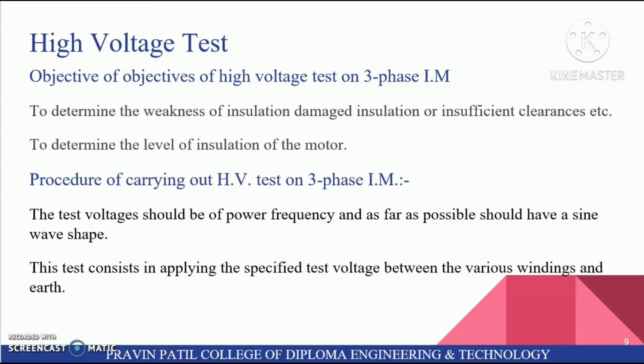Procedure of carrying out HV test on 3-phase induction motor. The test voltages should be of power frequency and as far as possible should have a sine wave shape. This test consists in applying the specified test voltage between the various windings and earth.